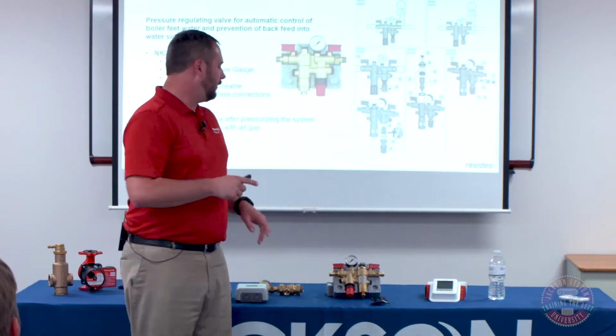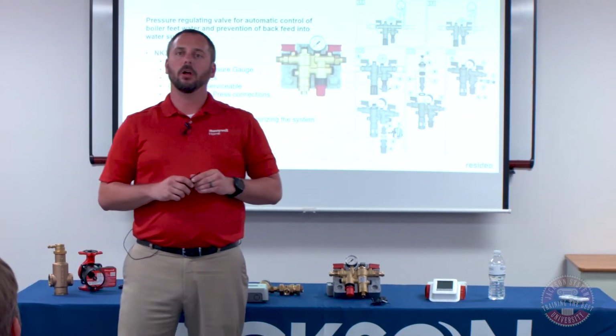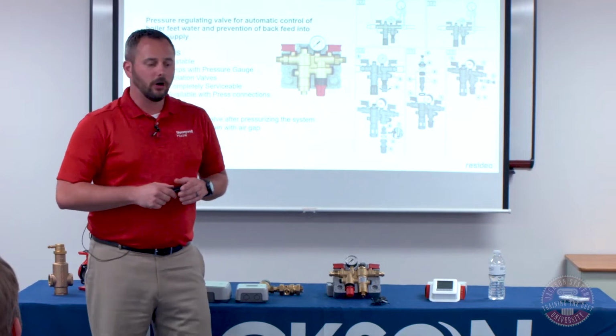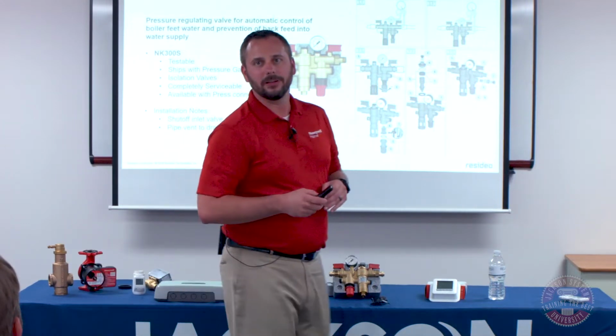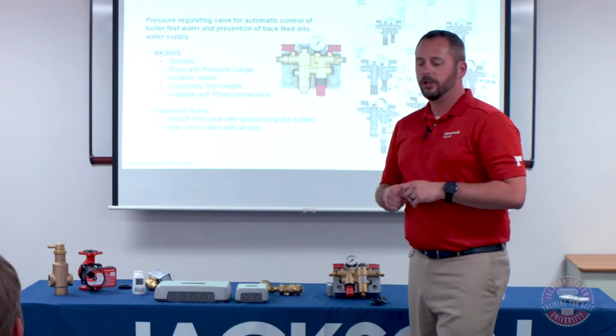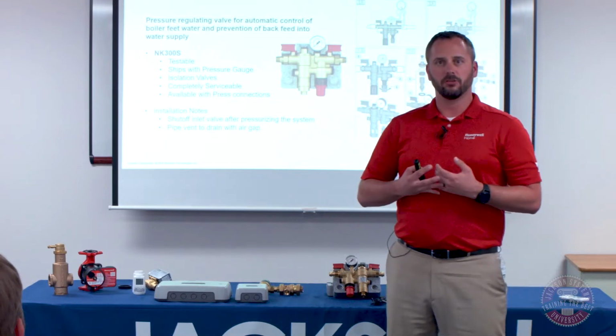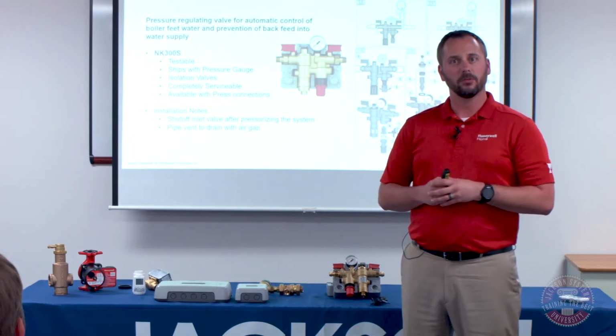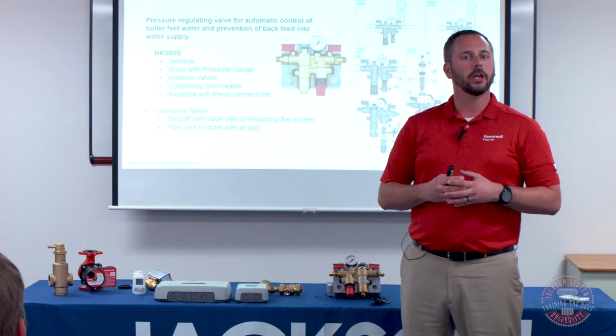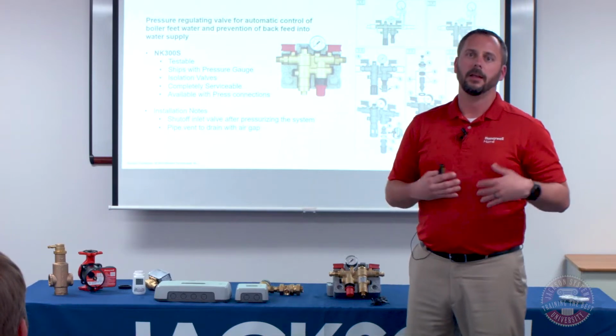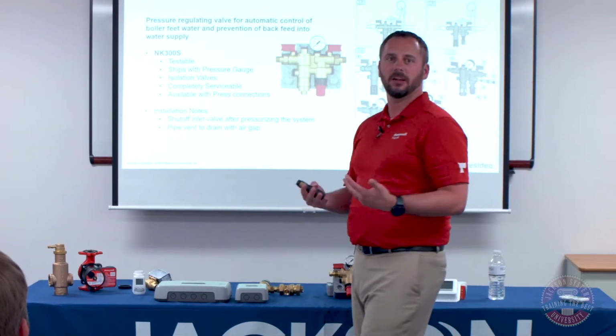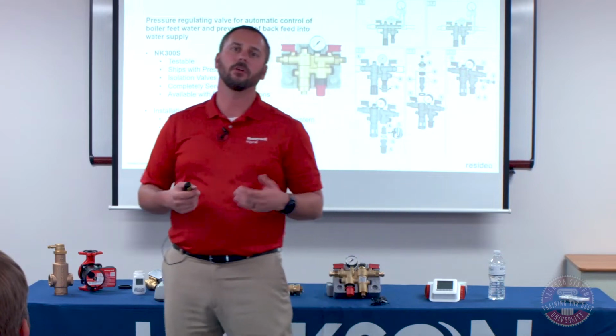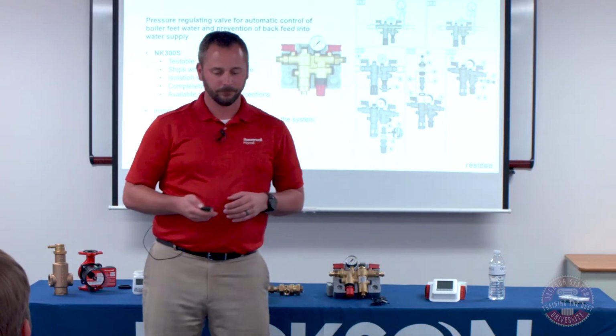The other thing that I didn't touch on, there's a couple black plastic plugs that are inside of there. Those aren't just for decoration. Those are actually test ports. So what you can do with this is you can take a differential pressure meter or some kind of a backflow test device, and you can actually hook it up to those test plugs. That gives you the ability to walk up and get a sense for if it's working or not before you have to take everything away.